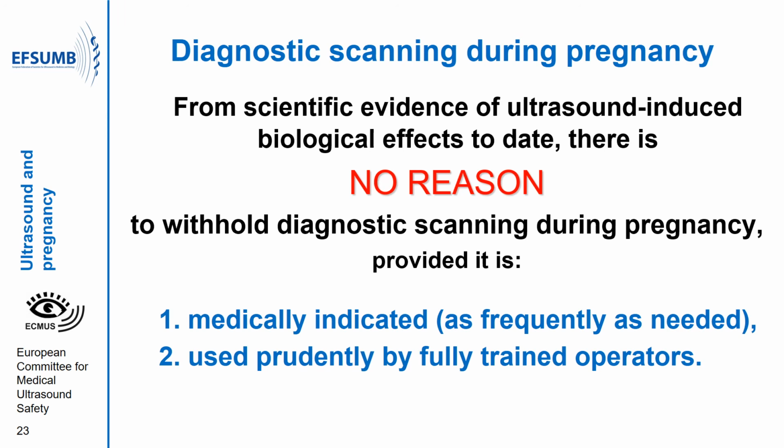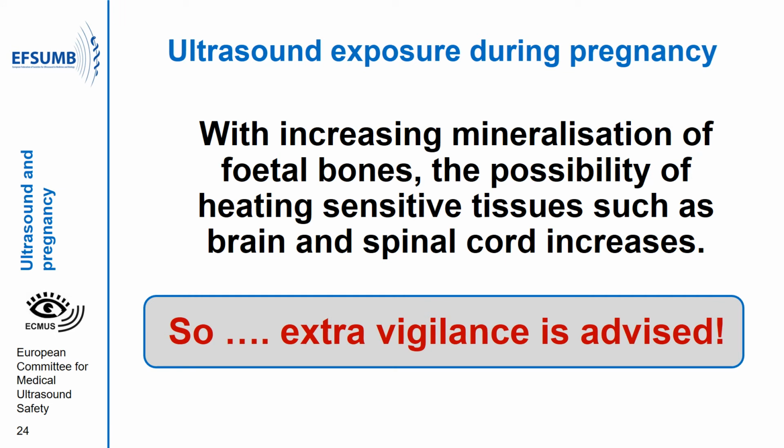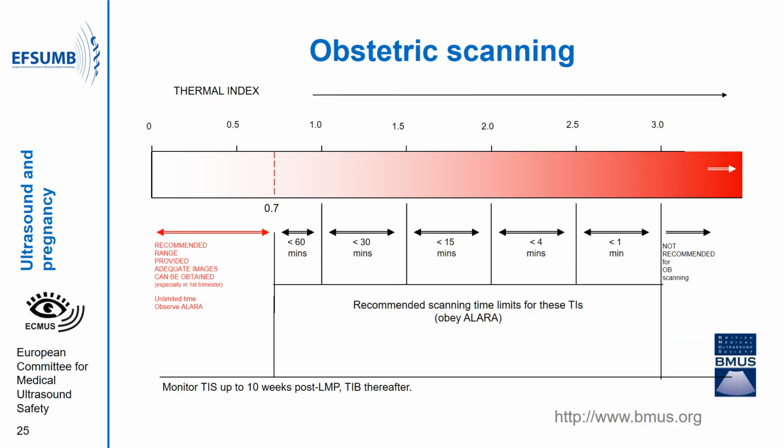For diagnostic scanning during pregnancy, there is no scientific evidence of ultrasound-induced biological effects, and therefore no reason to withhold diagnostic scanning during pregnancy, provided it is medically indicated and used prudently by fully trained operators. During pregnancy, fetal bones become increasingly mineralized, and therefore the possibility of heating sensitive tissues such as brain and spinal cord increases. Consequently, extra vigilance is advised. For obstetric scanning, the British Medical Ultrasound Society has linked the displayed value of TI to maximum scanning times. This helps to minimise the potential heating risk in routine obstetric scanning.